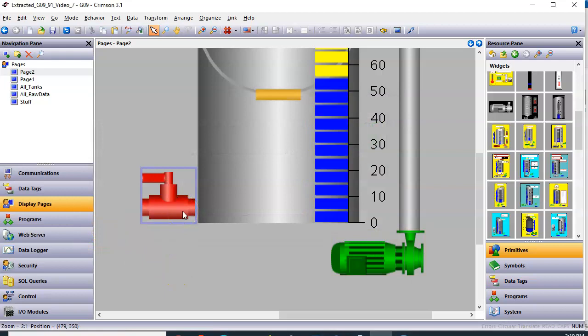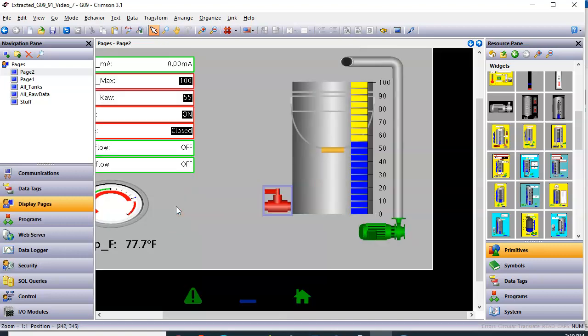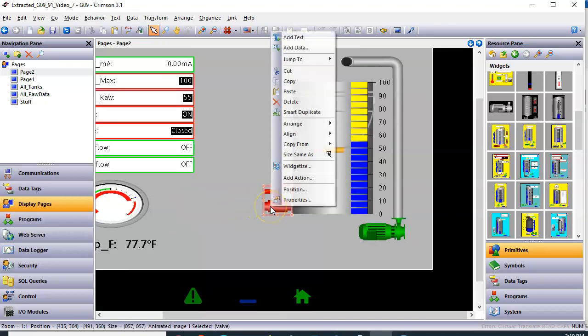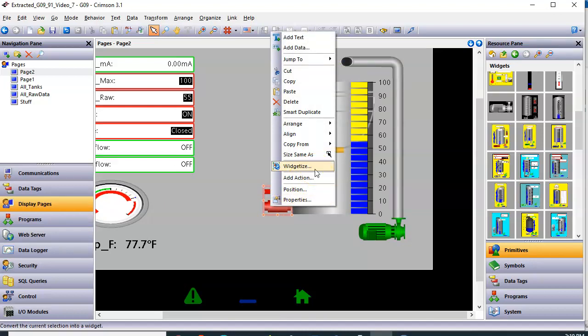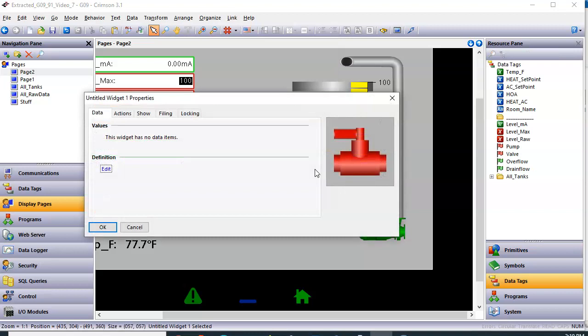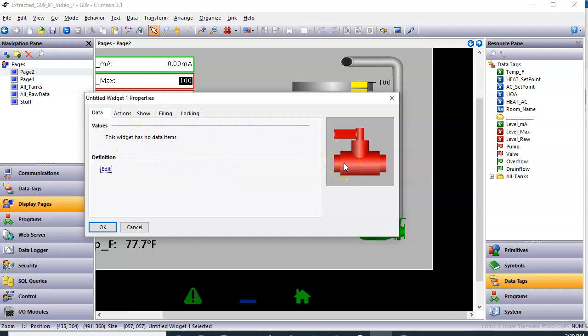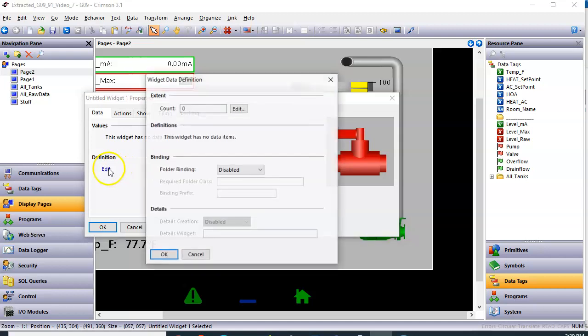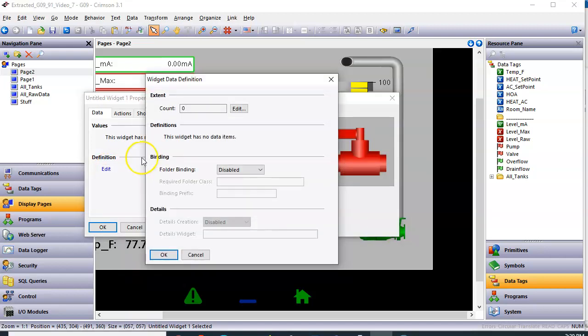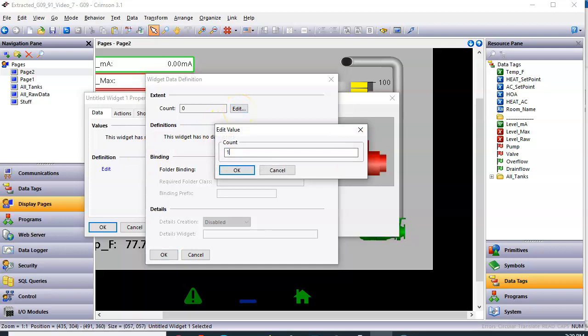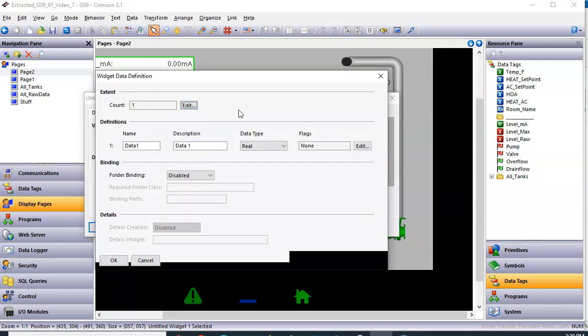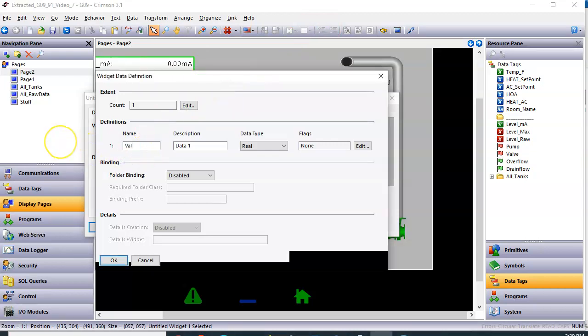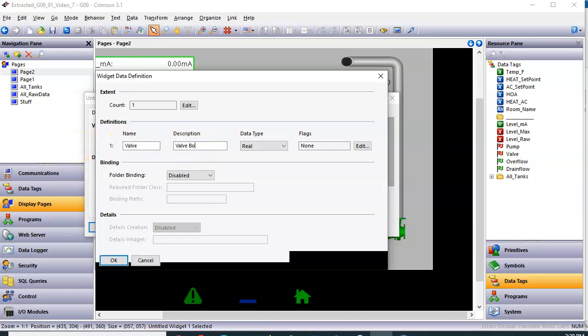Let's do the same thing now on our valve over here, just so you get a chance to build another one. So I'm going to right-click on the valve, and I'm going to go to the fourth thing from the bottom and click Widgetize. Once again, it says this widget has no data items. We know that this guy is interacting with one tag called Valve. So I'm going to click the Edit button here. I'm going to click the Edit button here for Count, and I'm going to declare a widget tag. This allows me to declare a widget tag. And I'm going to call this tag Valve. So I'll highlight this field, type Valve. And of course, the description, I can type Valve Bool Flag Tag.